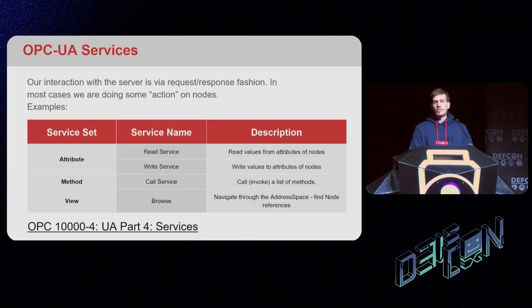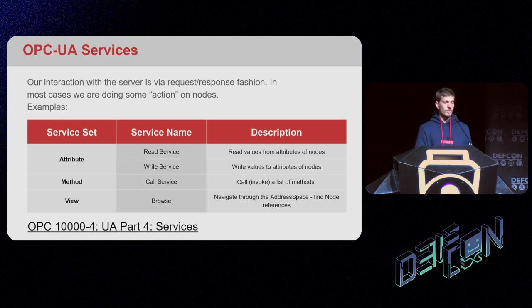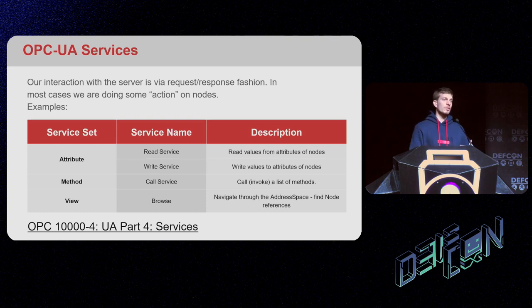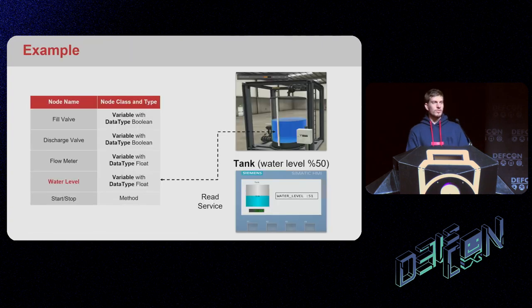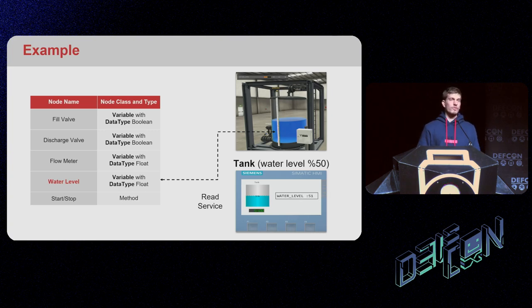In OPC UA we also have the concept of services — our way of interacting with the server. We can activate different services on different nodes. For example, to read a variable or tag we use the read service; to write to it we use the OPC UA write service. To implement OPC UA you need to implement a lot of these services. In our water tank example, the HMI continuously reads the water level variable using OPC UA's read service.